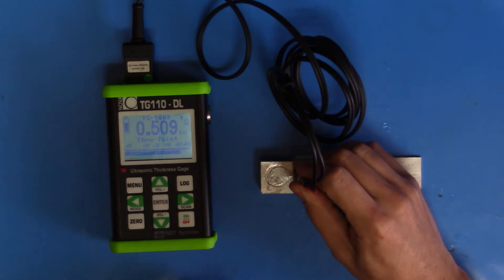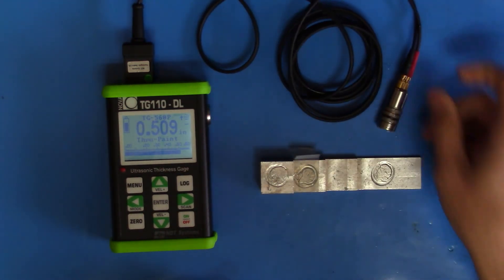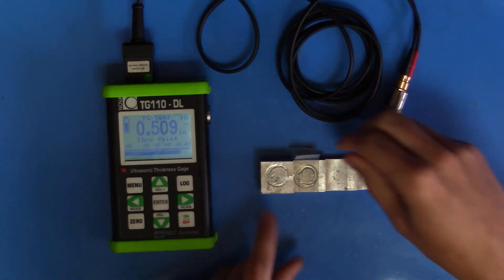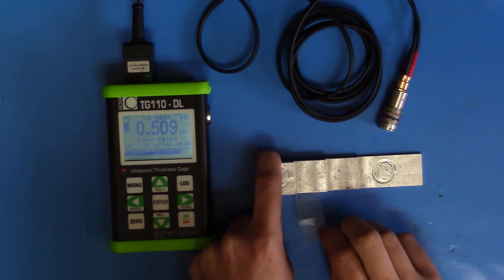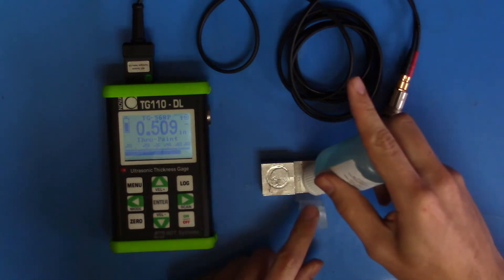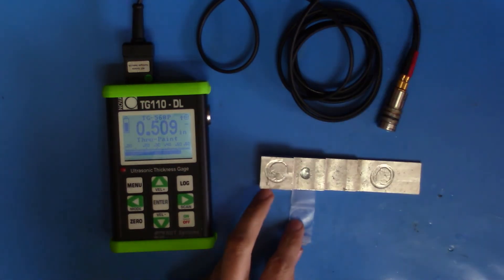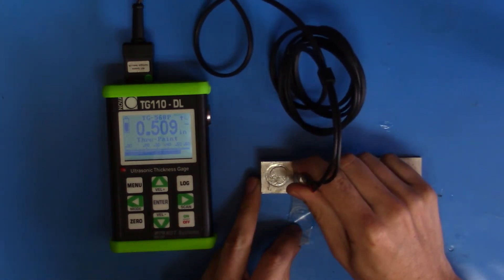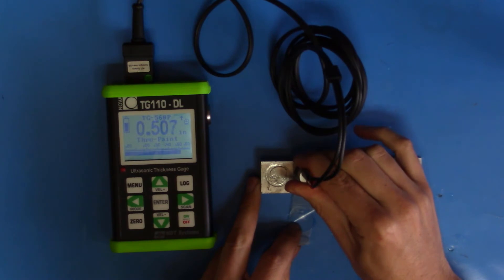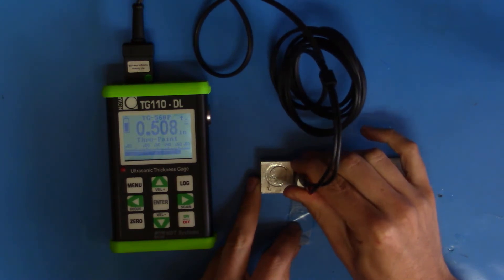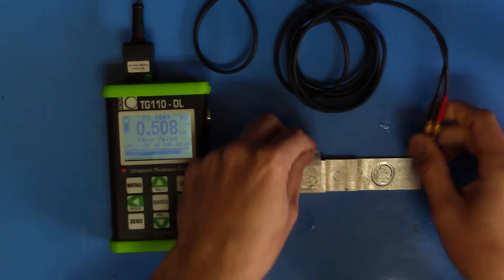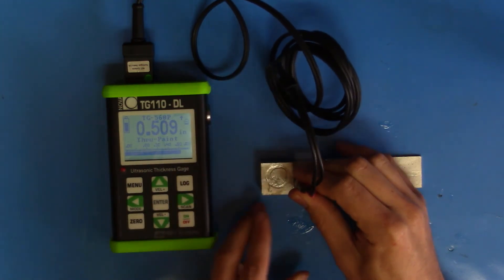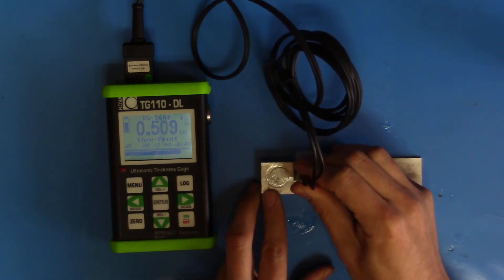We're going to get a nominal value of about 0.5 inches. We can verify that we're actually reading through the paint and not just including the paint in our readings by stripping away the coating. And the reading is very close. We can put our tape back just to make sure. And it's the same.